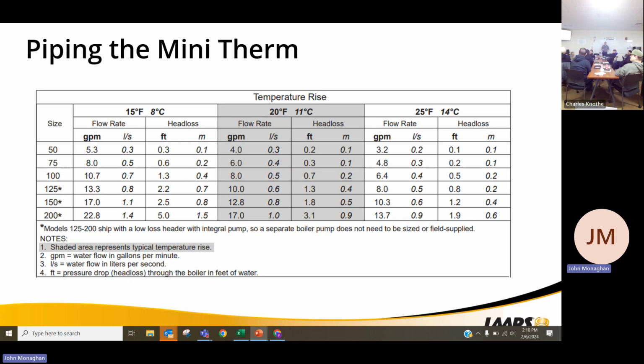We get into the smaller products, the 100, the 75, and the 50. Same thing. Rules come into play. 1 gallon a minute is 10,000 BTUs. Most of your standard home pumps are going to be just fine to move the amount of water required through the unit. 20-degree delta T, I need 6 gallons a minute. Most of your pumps are going to be more than capable of doing it, whether it's 007, 1558, B&G 100. Any of those pumps are going to be more than enough to move the water through them.